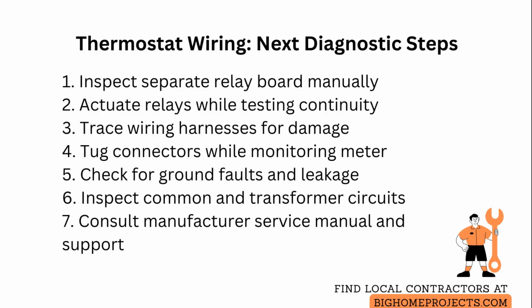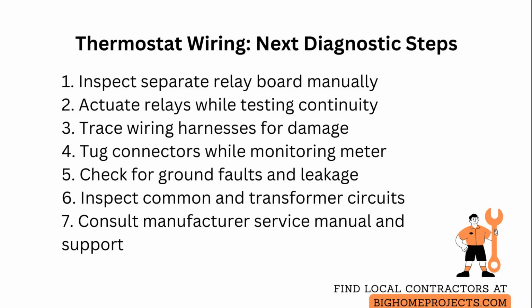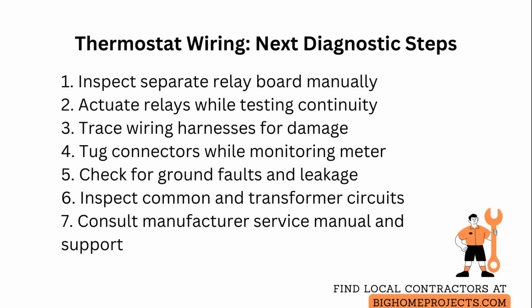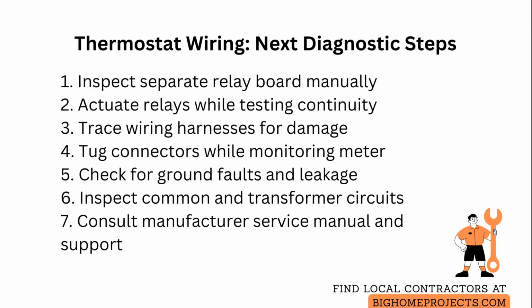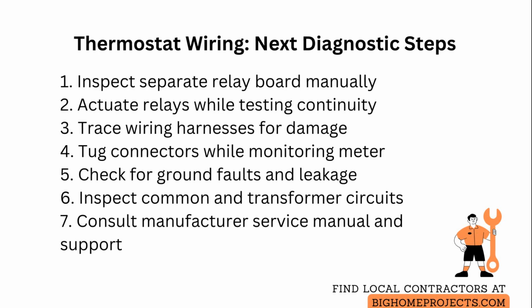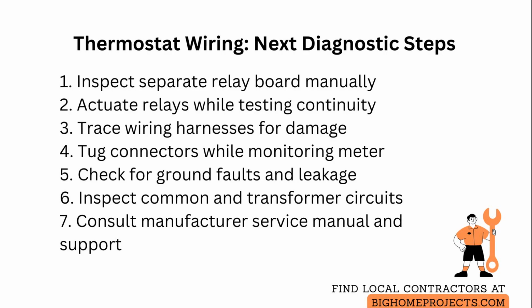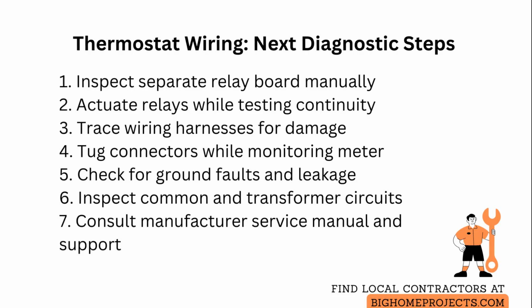Check for ground faults by measuring resistance between key control circuit grounds and chassis ground, and by looking for stray voltages with the system powered and the thermostat calling. A few volts, where you expect none, indicates a leakage path. Inspect common and shared circuits like the equipment common or transformer secondary, because a partially shorted common can allow sensing circuits to behave erratically without a full-blown short.